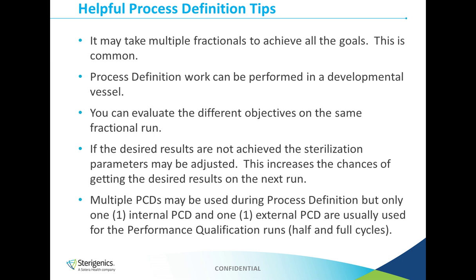Now, if you choose to do this, one of the reasons you would is because in that smaller vessel with that smaller load configuration, it's a lot easier to get fractional growth than, let's say, with a 30-pallet load, where that product is holding on to the EO and the heat, so it's probably going to give you more kill.